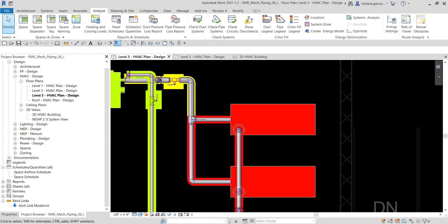Important note: errors may occur while attempting to create pipe geometry as a result of converting a layout or during sizing. The most common cause is insufficient space to create the pipe, or incorrect offset elevations. To resolve this, either relocate the system components, select a different layout solution, or manually modify the pipe. Always remember to check pipe connectivity after any modification.